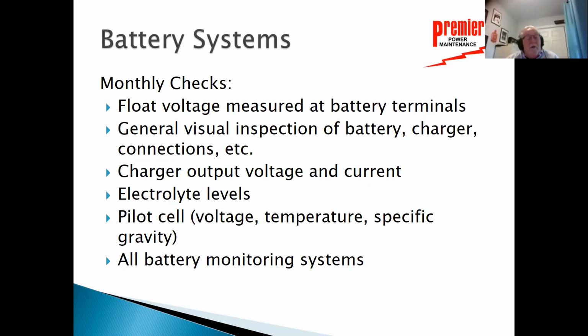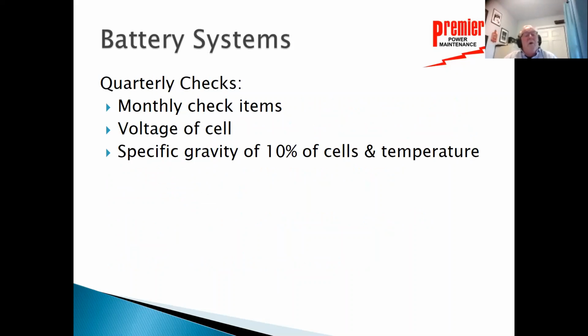Check the charger output voltage and current. Monitor the electrolyte levels, and do a pilot cell. Take voltage, temperature, and specific gravity of that pilot cell, and make sure all your battery monitoring systems are operating correctly. Doesn't take much time, but you have to get to your various sites to do that. Then on a quarterly basis, do all those monthly checks, and then do voltages of the cells, and 10% specific gravity. Do the specific gravity of at least 10% of the cells, and the temperature along with those.